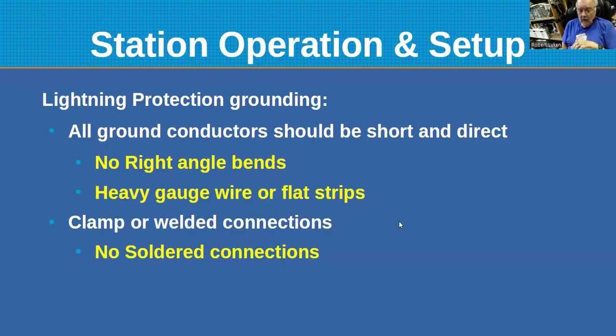A lot of people, when they do connections to ground rods, and you can have multiple. In fact, ideally, like for a commercial installation, you would have ground rods and ground wire around the whole circumference of the property. You can actually get this material, it's like a thermite, and put it on those connections, and it burns and creates enough heat that it actually makes a welded connection. It's not solder, it's physically welded. It melts the metals together.